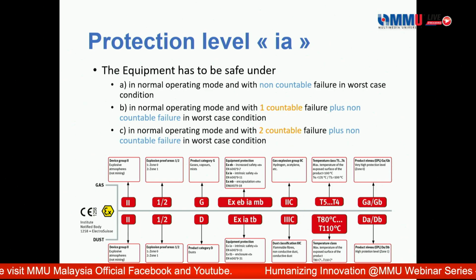If you want your equipment to have protection level IA, it needs to fulfill three criteria: it must survive in the worst case under a non-countable fault, and it must also survive under one countable fault and two countable faults. If two countable faults are required, your circuitry would need three Zener diodes, for example.